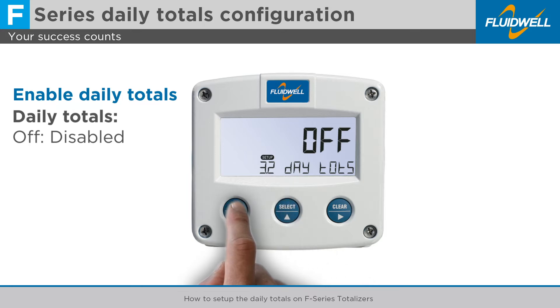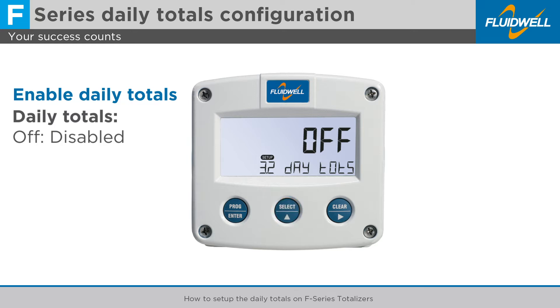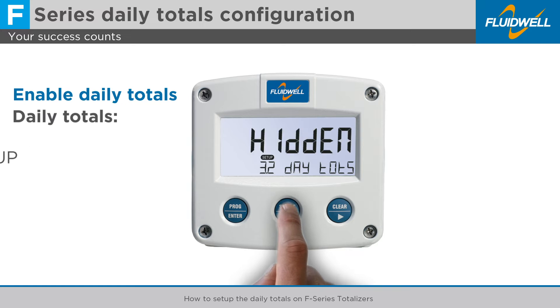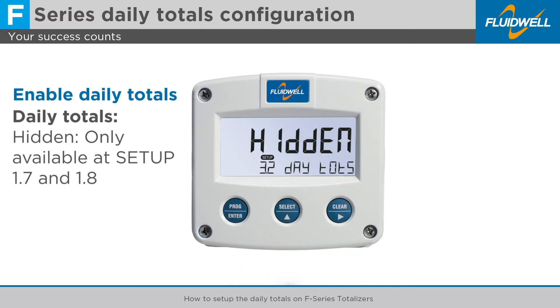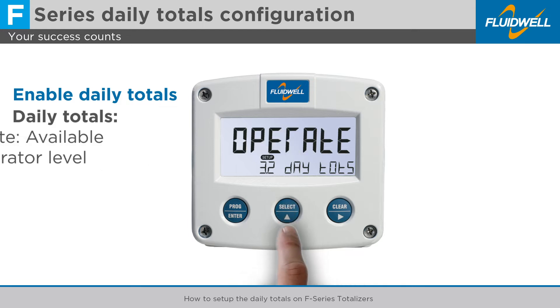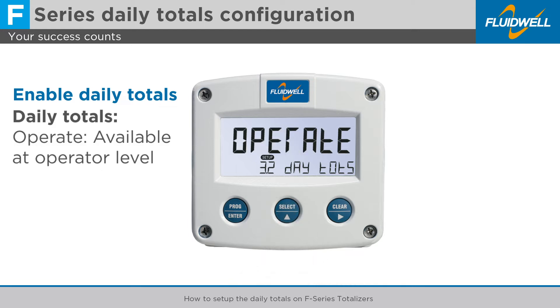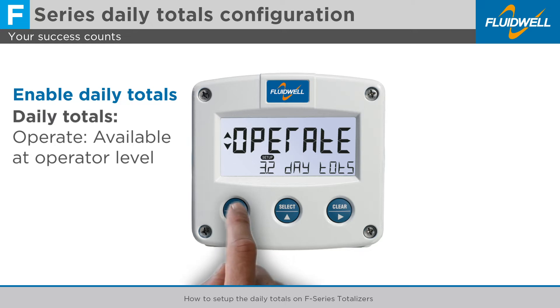Press prog to change this setting. Press select to see the settings: Off — daily totals disabled; Hidden — daily totals are only available at setup 1.7 and 1.8; Operate — daily totals are available at operator level. Press prog to store this setting.